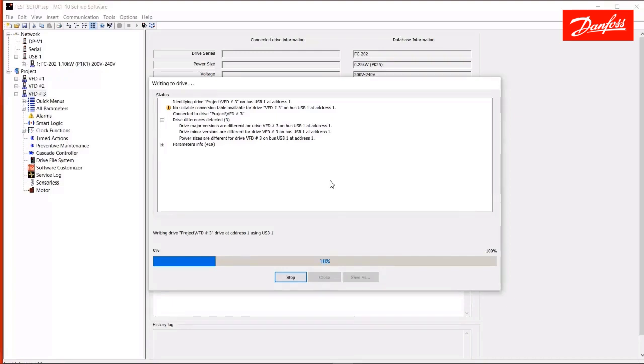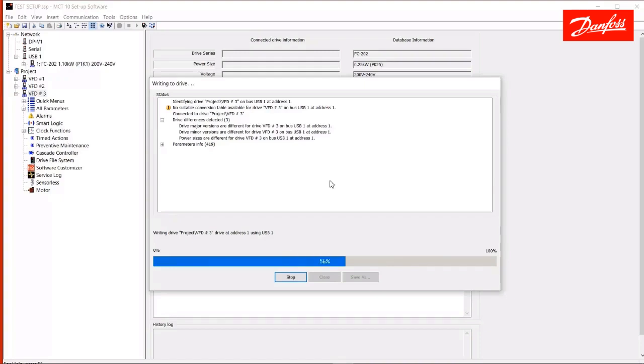If you are able to match the software versions, then the software versions, the voltage and power size, you should get 100% right without any warnings or errors. If you do select a wrong value for the software version, like I mentioned, then you may get some errors. And after the write's complete, you'd want to go and make sure that everything that you wanted to wrote correctly. But, normally, it will.